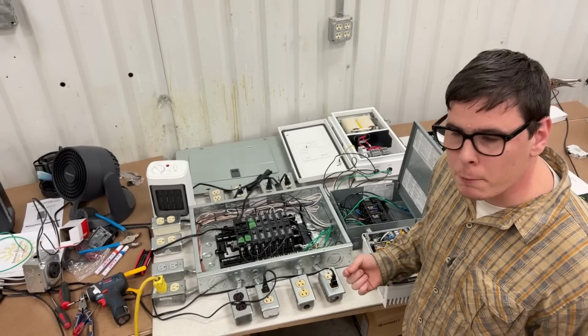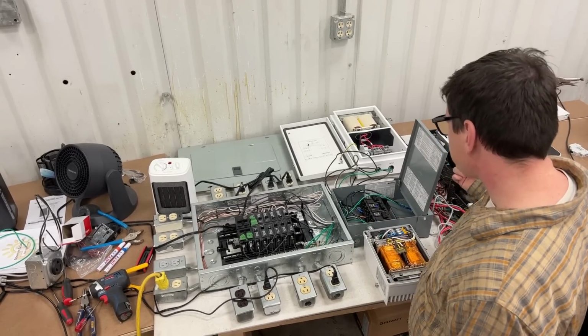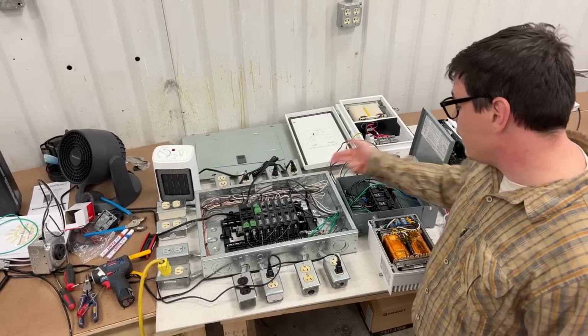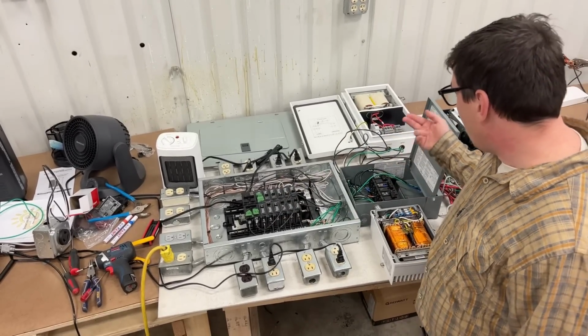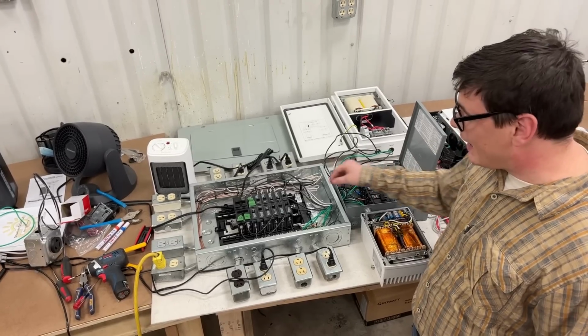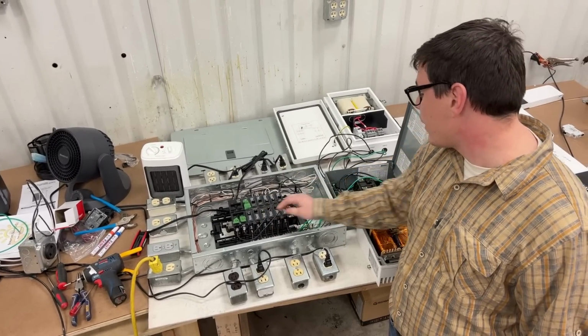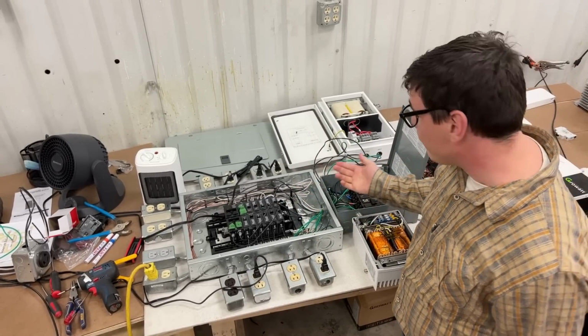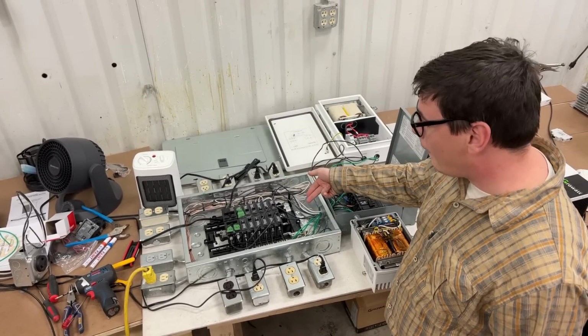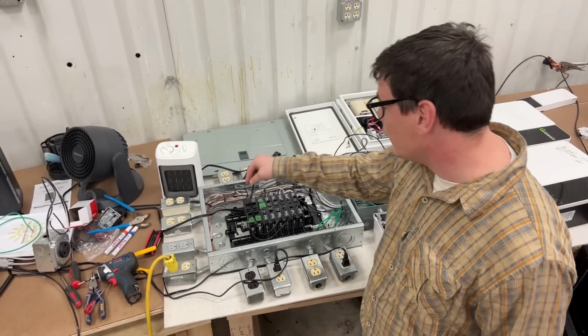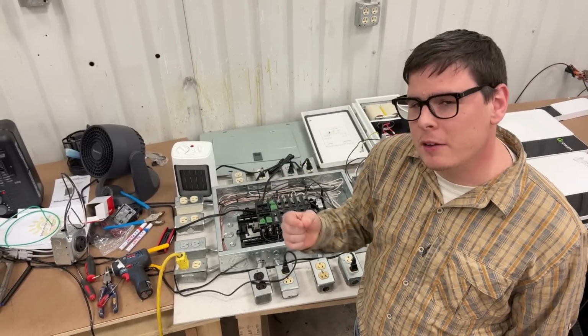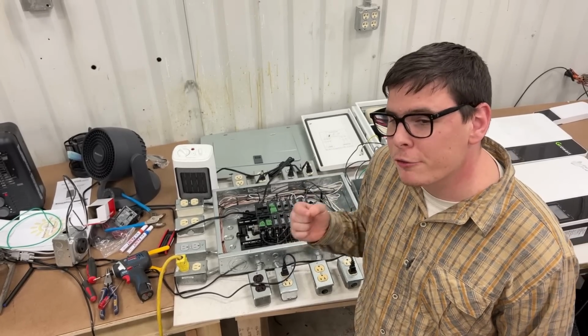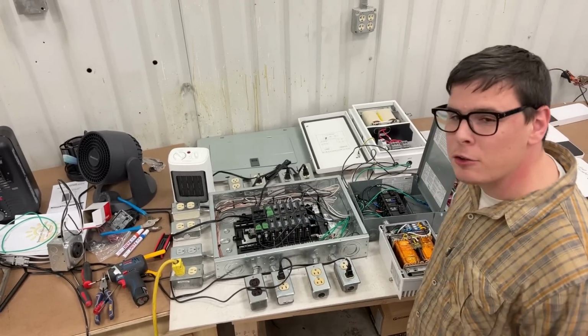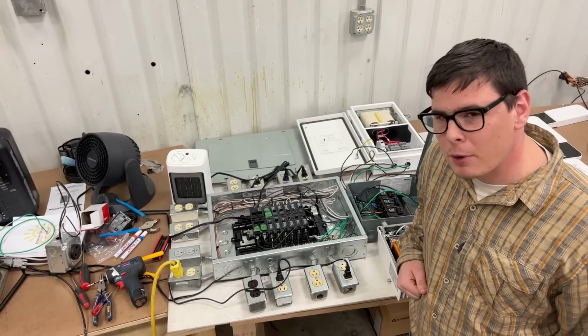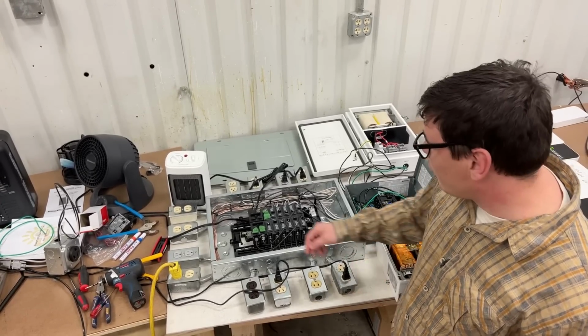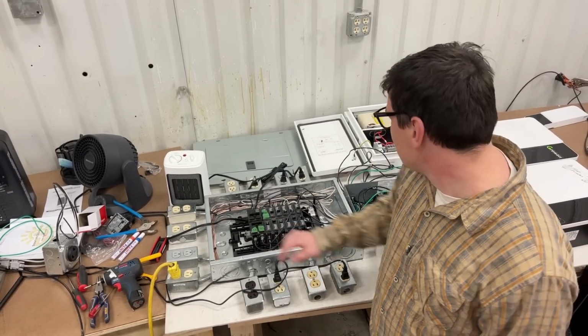It's a little messy, actually really messy, but I've got the transformer and inverter in on this breaker panel. Now I could have 5 inverters on this breaker panel, and 1 transformer if I want, or 2 transformers, whatever's appropriate, okay? And what I've got here is I'm feeding this breaker, but the thing is that I come out of this breaker panel into my input breaker on this panel, which, because, I don't know, somehow we went cheap, we should have had a main breaker, but you wouldn't use a main breaker because you would land it on a breaker that corresponds to the amperage rating of your number of transformers.